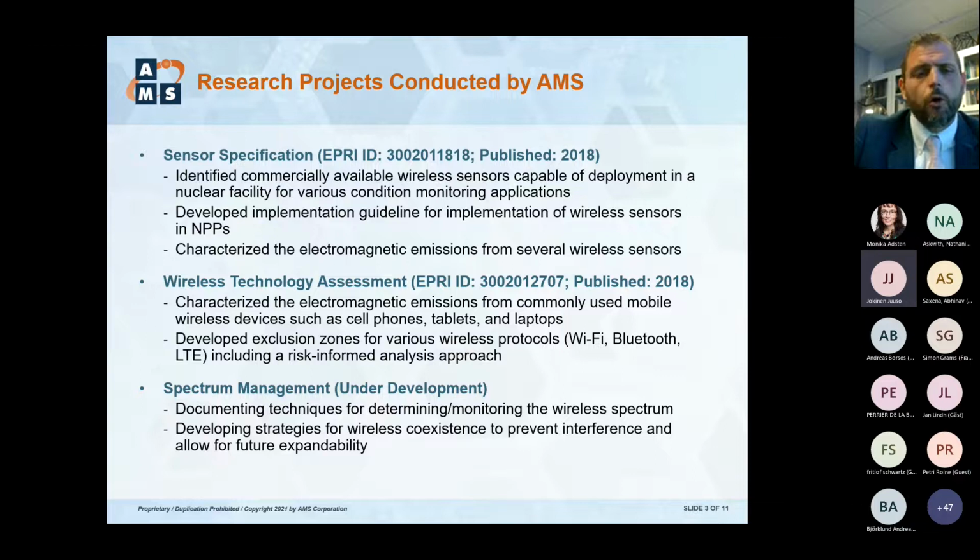And really part of the goals with this is traditionally, at least here in the US, they've used exclusion zones or exclusion distances to define distances that you must keep devices away from plant equipment. A lot of this spawned from walkie-talkie radios back in the 80s. So a plant may have experienced a trip because security or operations keyed a radio and tripped the unit off. So they developed, hey, we're going to keep these devices away from sensitive plant equipment by X feet, maybe 15 feet or 5 meters. Well, going along with that, they adopted this exclusion distance calculation.